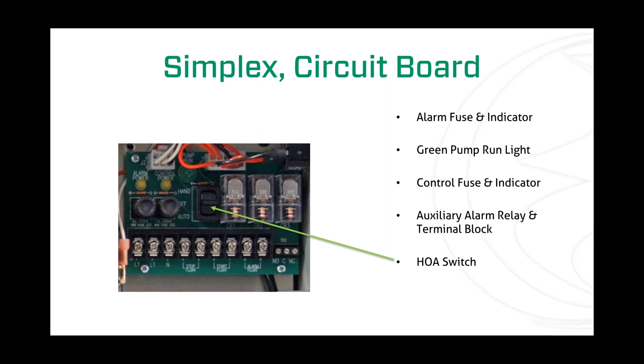Another piece here is the auxiliary alarm relay and the terminal blocks. These terminal blocks are where you're going to wire up your incoming power, your float switches, all that sort of stuff, all your field wiring. And then the last thing I'll point out is the HOA switch, your hand-off-and-auto position. You'd be surprised the number of phone calls we get from people who think they have a control panel problem, when the problem is that they don't have that HOA switch in the correct position. Anyway, it's a handy little thing and pretty important.